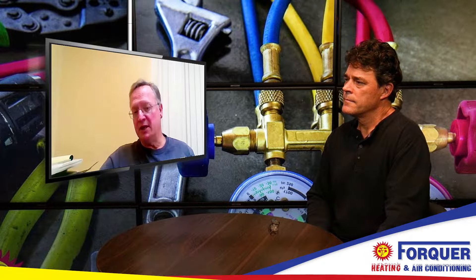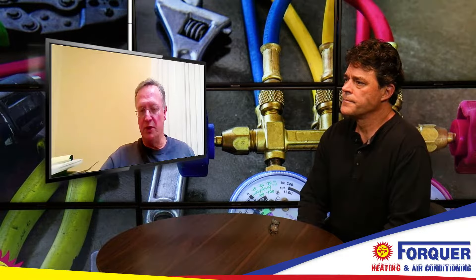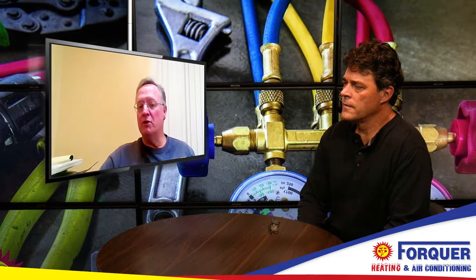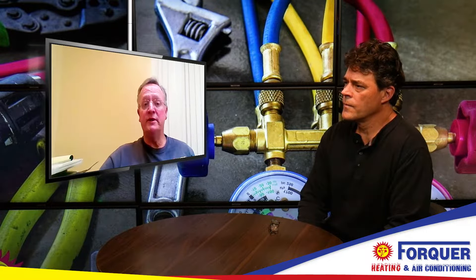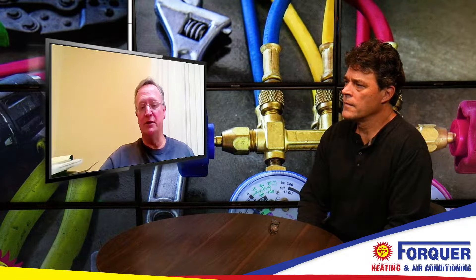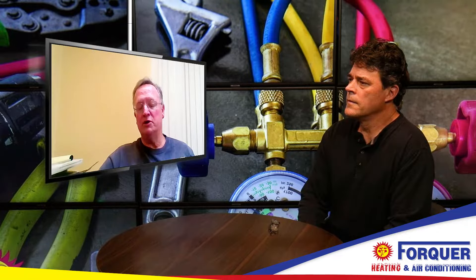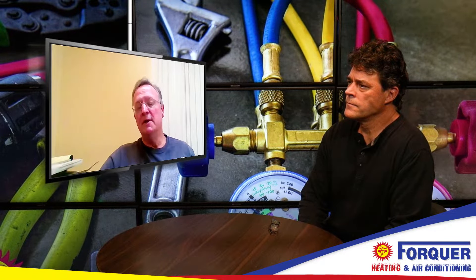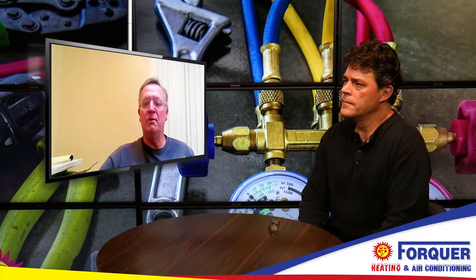Now we're going to check the safeties — if it's a gas burning furnace, we're going to make sure that house isn't going to blow up or burn down. We're going to clean the flame sensor, which is routine and is usually a very common failure point. All furnaces now are direct ignition, and cleaning the flame sensor is a must-do. We're going to check the motors to make sure the bearings are good and they're clean, check the draft to make sure it's not spilling, then take a combustion analysis. If the furnace has over 400 parts per million carbon monoxide in the exhaust gases, the gas company considers that an unsafe appliance — we need to know that.